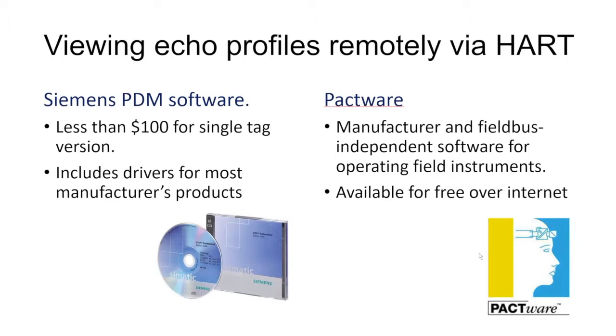Besides having the integral display that can show echo profiles, there are a couple ways we can take a look at it remotely via HART. Siemens offers a software package called PDM available for less than 100 dollars for the single tag version. PDM includes all the drivers for all the Siemens products and probably hundreds if not thousands of drivers for other manufacturers products also.